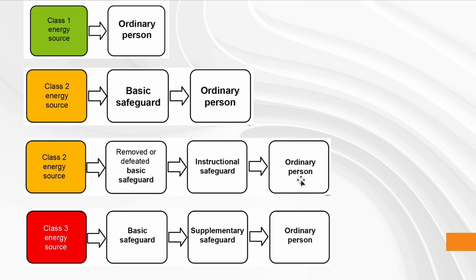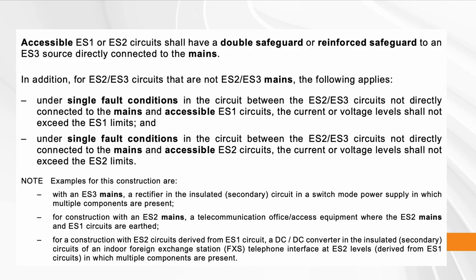The instructional safeguard must also say to make sure children do not access the product when you remove the safeguard. If there is a class 3 (ES3) energy source, this is very serious — it requires both a basic and a supplementary safeguard. Just one basic safeguard is not sufficient to protect an ordinary person from injury.